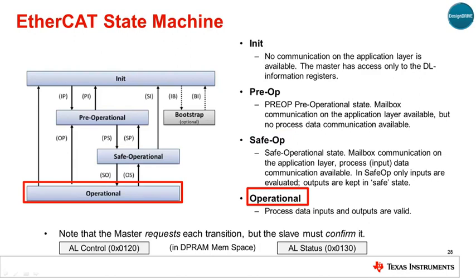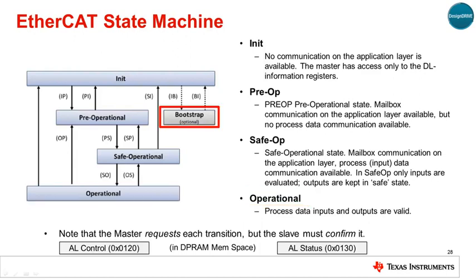In the operational state, all process data inputs and outputs are valid — in a factory, the machine would now be fully operational. A fifth state, bootstrap, is optional but is recommended if firmware updates are necessary. Note that in operation, the EtherCAT master requests each transition, but the slave must confirm it. These current transactions are reflected in the AL control and status registers, respectively.